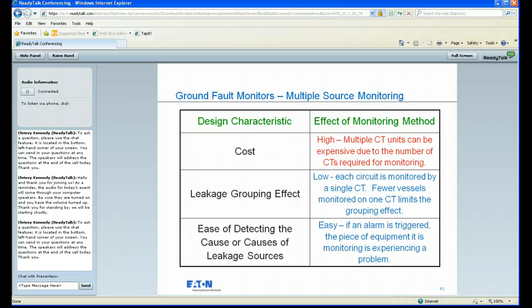From a cost standpoint, compared to the single source monitoring, the cost is higher. Multiple CTs can be expensive due to the number of CTs that are required. So basically, for each circuit breaker, you're going to have its own CT. When you get into larger panel boards that may have up to 20 circuit breakers in them, that's 20 more pieces of equipment you're going to need to buy.